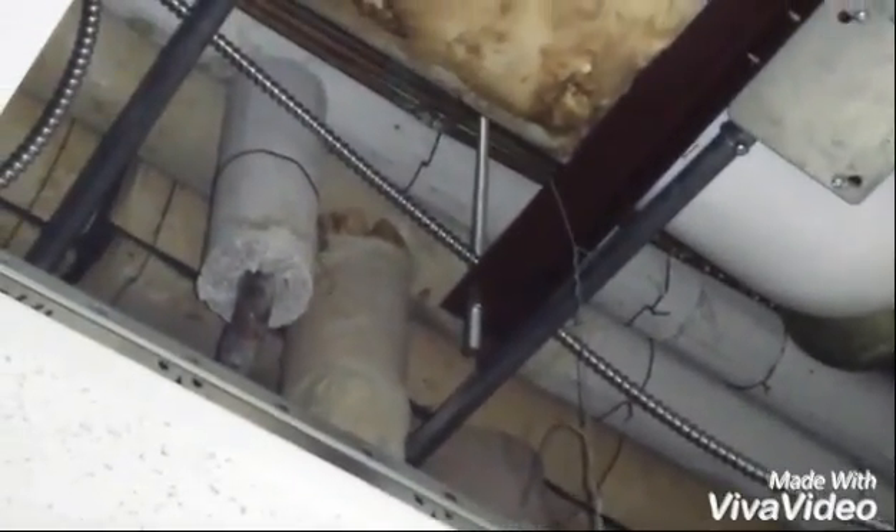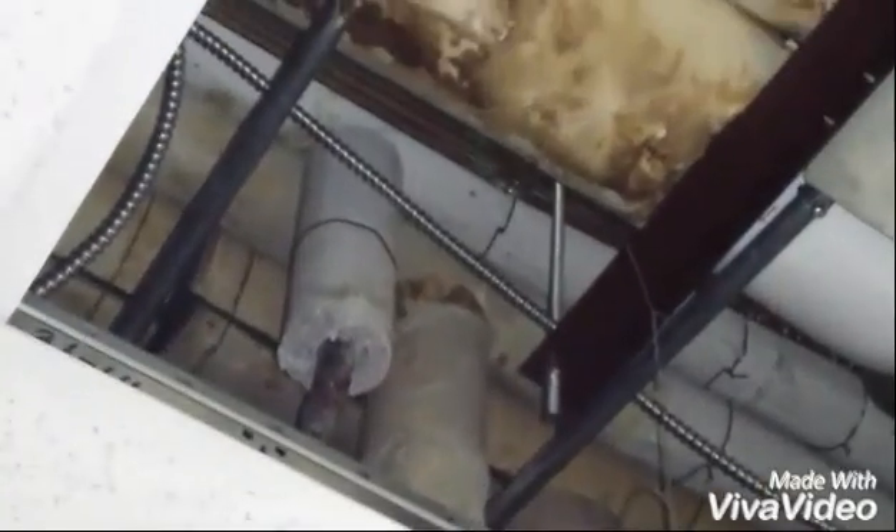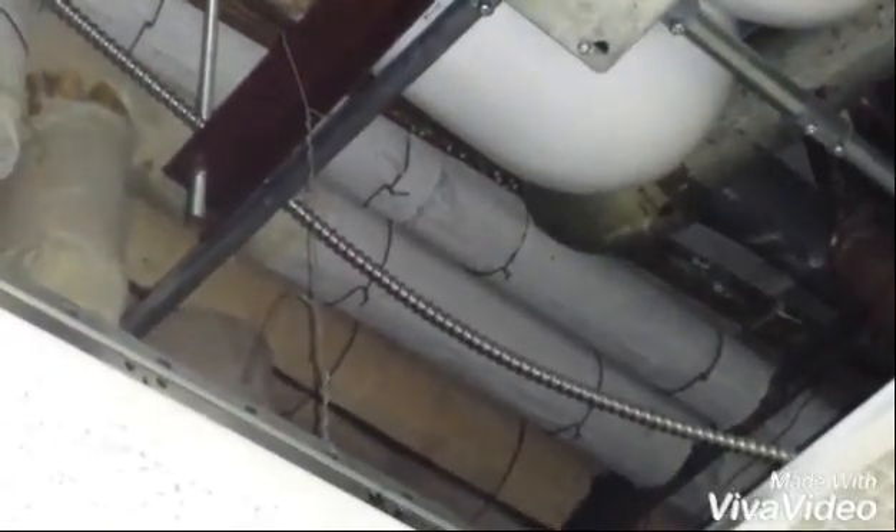It's like cardboard corrugation with pure loose asbestos inside, and it's open like that. When the pipes bang again, or anybody lifts tiles or moves them, it comes out of there. Those ends aren't sealed, the joints aren't sealed. The cracks between — they're not sealed — so everything leaks asbestos.